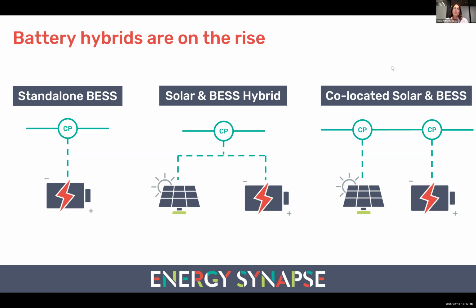When we say hybrid, we mean you've got more than one asset behind the same connection point. And what typically happens in a hybrid is that the total size of your assets is actually bigger than the capacity of the connection point itself. For example, you might have a 200 megawatt connection, and behind that a solar farm and a battery with a total capacity of 300 megawatts. So your total asset capacity very often exceeds the maximum capacity at the connection point.